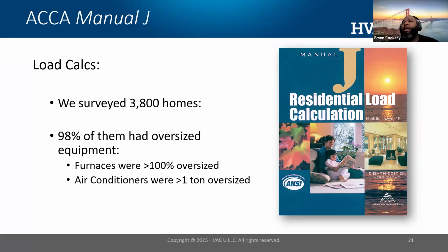What you see on your screen here now is ACCA Manual J. This is a design standard for heating and cooling professionals, and this standard has been around for decades. However, its adoption is very poorly used. And what I mean by that, there are all kinds of reports all over the place where as many as 50%, 60%, some reports say 70% of the residential systems in America are improperly sized.